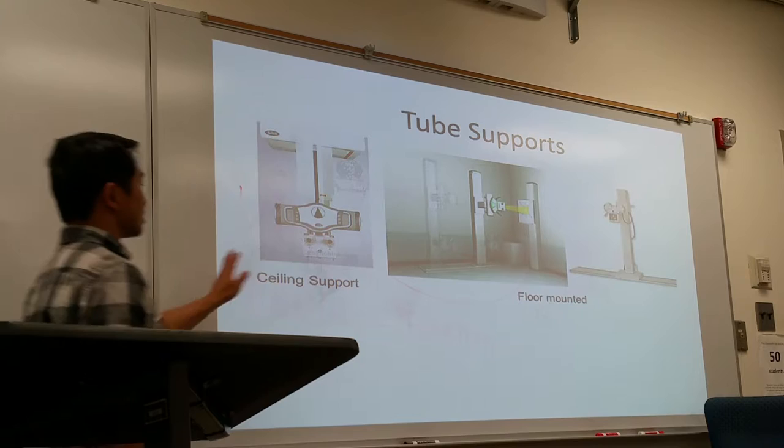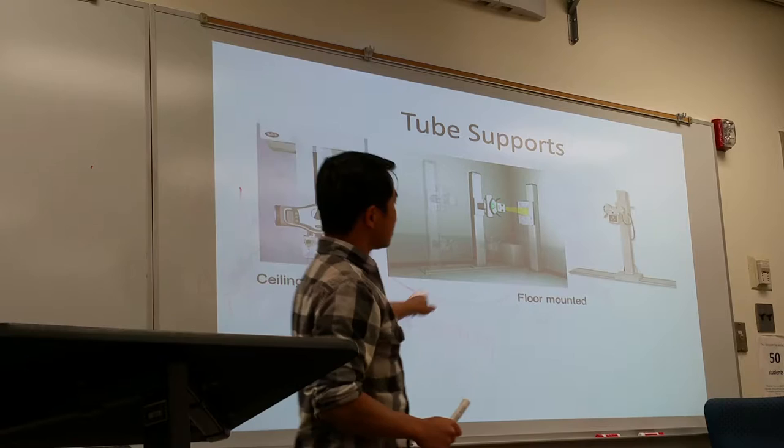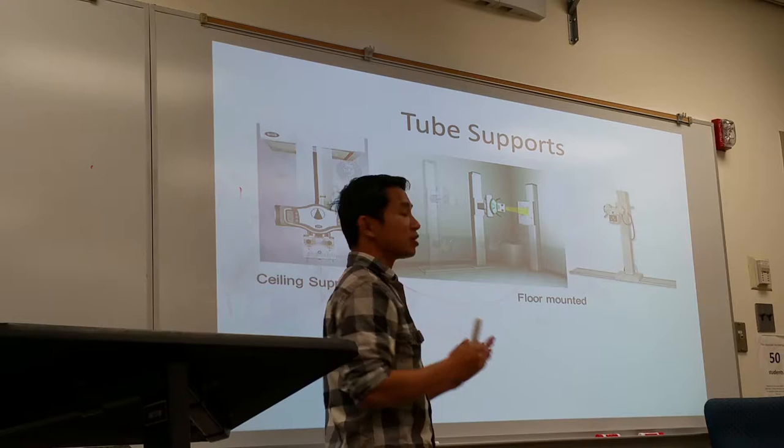Here are some images showing ceiling and floor support systems. The ceiling-mounted x-ray tube is part of a telescoping device — it goes up and down and can move in any direction. The floor-mounted tube just slides back and forth along a rail, which is very limited in terms of where you can manipulate the x-ray tube.